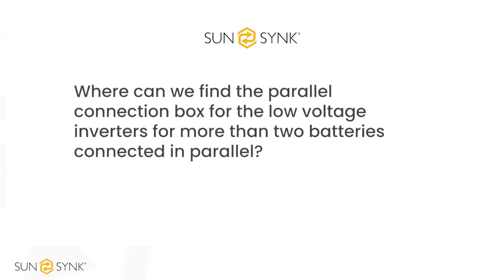That's correct. Where can we find the parallel connection box for low voltage inverters for more than two batteries connected in parallel? As a manufacturer, we say if you're using more than 3 batteries connected to one inverter, or multiple inverters connected in parallel, we always recommend using a common DC bus bar, because on all of our low voltage batteries, the parallel leads that we supply with them as standard are only 25 mil square. As we've covered in the presentation, on some of our batteries we can have up to 32 connected in parallel. And obviously, if you've got 32 batteries connected in parallel on 25 mil square, we're going to have quite a big problem. So if you are using multiple batteries, whether it's one inverter or multiple paralleled inverters, always use a common DC bus bar.